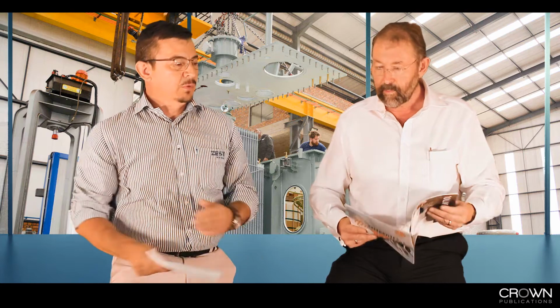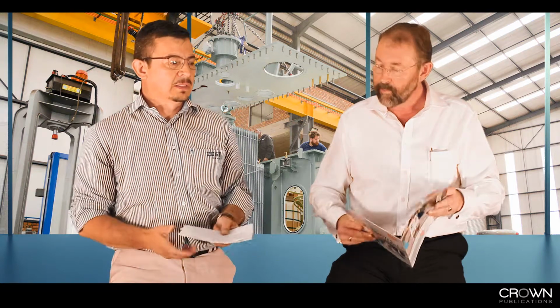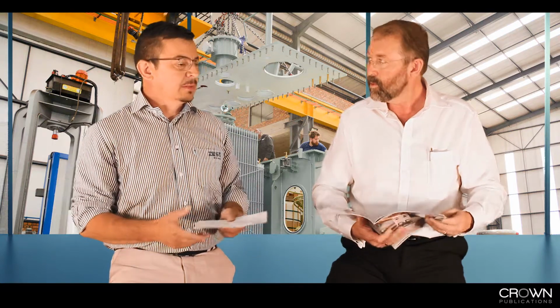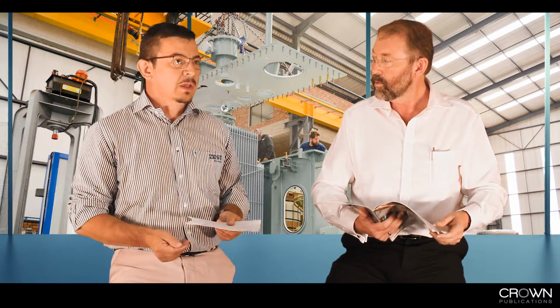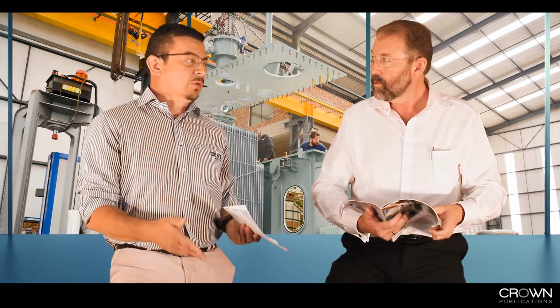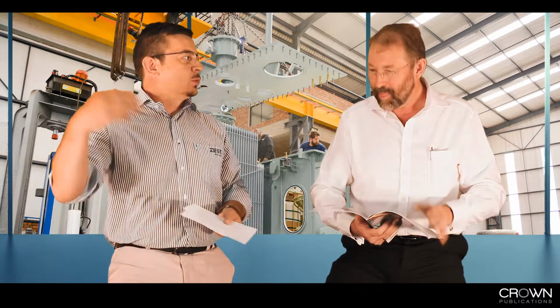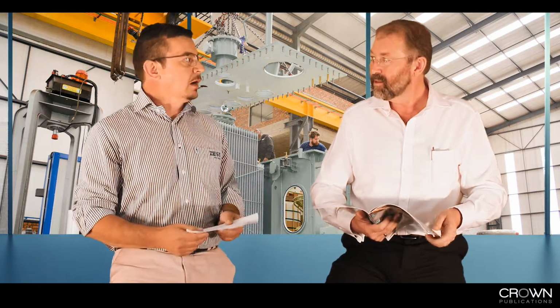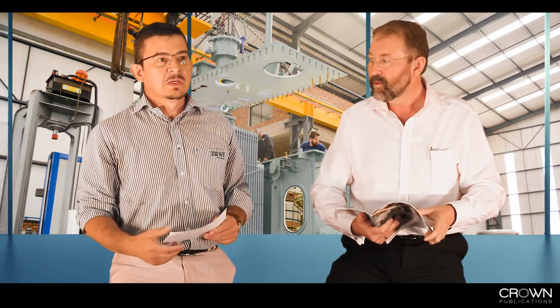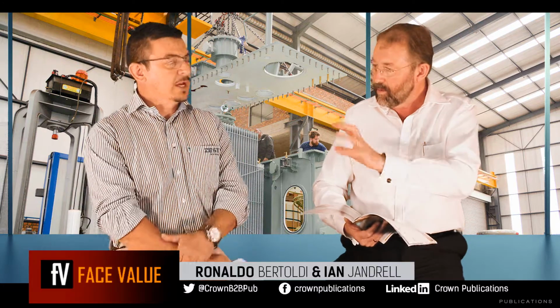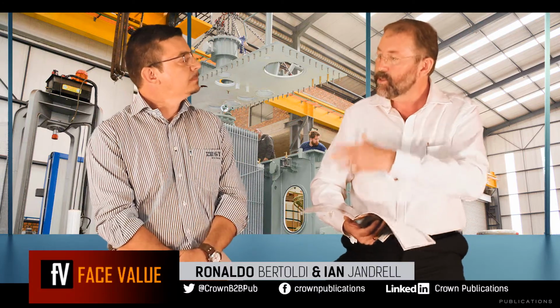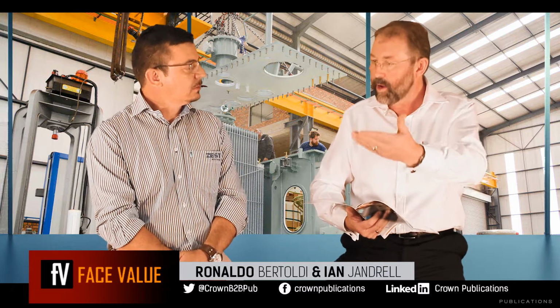If you operate the transformer in a stable environment, it'll be very comfortable for the transformer. But if the temperature changes from minus 10 degrees to 45 degrees, it's very hard on the transformer, and this must be taken into consideration when you size it. And you would design to accommodate that, providing you're aware of the application.